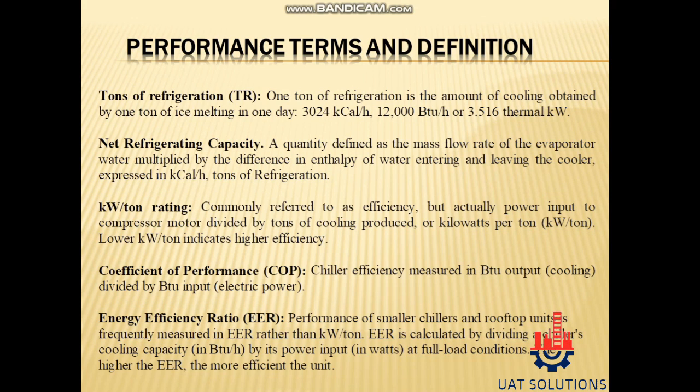Net refrigerating capacity: a quantity defined as the mass flow rate of the evaporator water multiplied by the difference in enthalpy of water entering and leaving the cooler, expressed in kcal per hour or tons of refrigeration. Kilowatt per tonne rating: commonly referred to as efficiency, but actually power input to compressor motor divided by tons of cooling produced, or kilowatts per tonne. Lower kilowatt per tonne indicates higher efficiency.